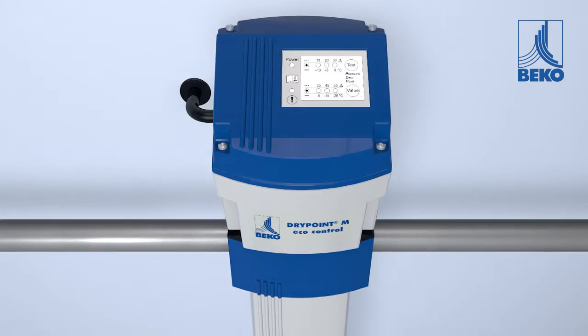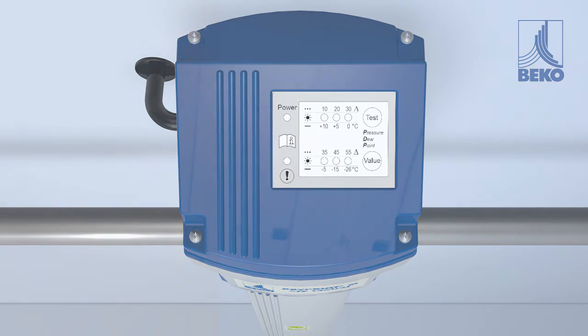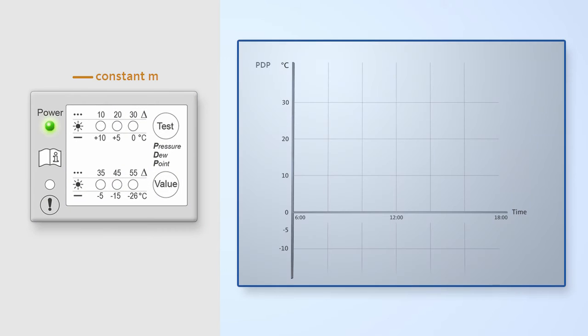The desired operating mode is selected via a clearly laid out operating panel. If the power LED is permanently lit, then constant mode has been selected. The green LED in the scale range displays the currently set pressure dew point. Shown here, plus 10 degrees Celsius or minus 5 degrees Celsius.